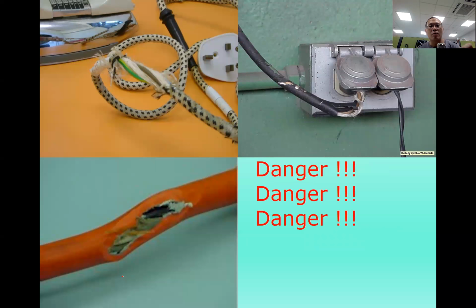So this is what I mean by exposed cable. The insulating material is worn out, but the important thing is that the cables, even the live wires here, are being exposed. So that's one of the dangers we are talking about.